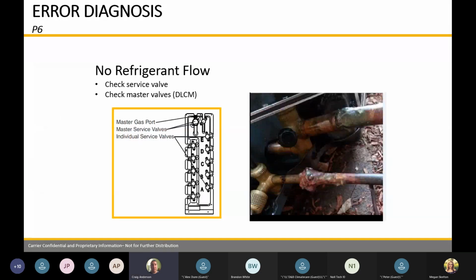So here, no refrigerant flow. If you ever had to weld any of these lines, if you're running over 50 feet and you're welding them together, make sure we're putting nitrogen through the line. You're getting enough heat. We're not blotching up the Freon or the line when we're doing the welding. Like I said, master ports, make sure they're fully open, and then each of your individual ports are open. So if you have a 2-zone system, you're opening 6 ports on that baby. Make sure they're all open.